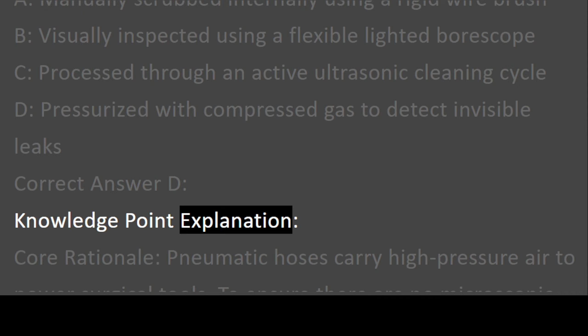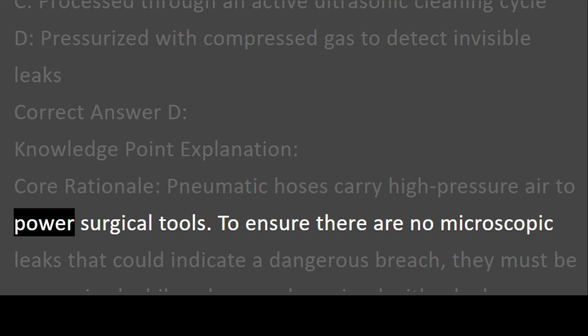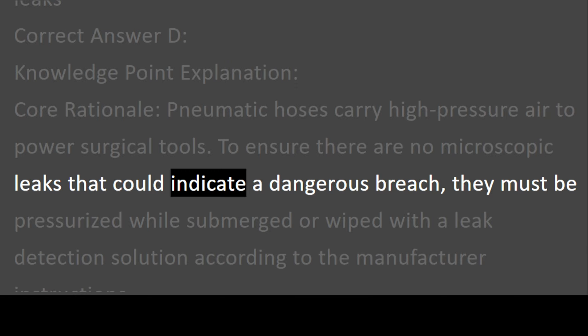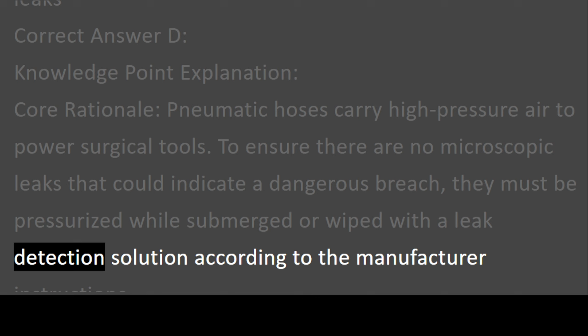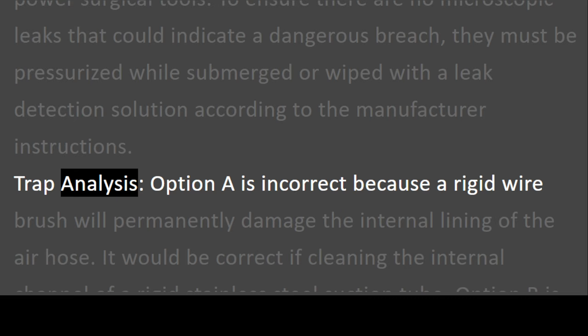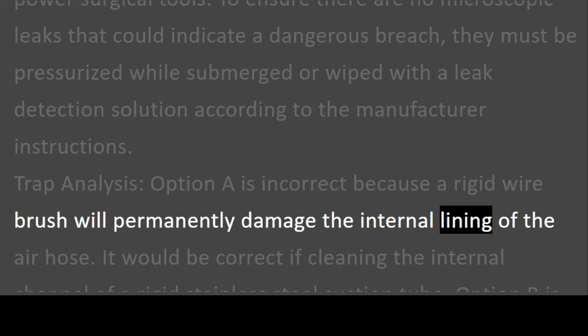Correct answer D. Knowledge point explanation. Core rationale: pneumatic hoses carry high-pressure air to power surgical tools. To ensure there are no microscopic leaks that could indicate a dangerous breach, they must be pressurized while submerged or wiped with a leak detection solution according to the manufacturer instructions. Trap analysis: option A is incorrect because a rigid wire brush will permanently damage the internal lining of the air hose. It would be correct if cleaning the internal channel of a rigid stainless steel suction tube.